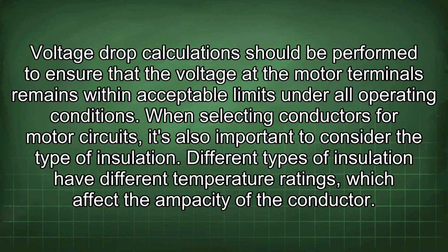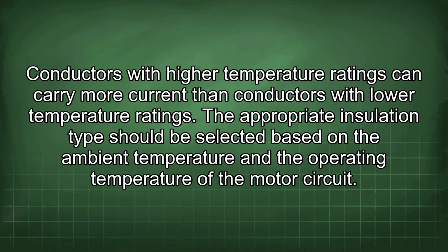all operating conditions. When selecting conductors for motor circuits, it's also important to consider the type of insulation. Different types of insulation have different temperature ratings, which affect the ampacity of the conductor. Conductors with higher temperature ratings can carry more current than conductors with low temperature ratings. The appropriate insulation type should be selected based on the ambient temperature and the operating temperature of the motor circuit.